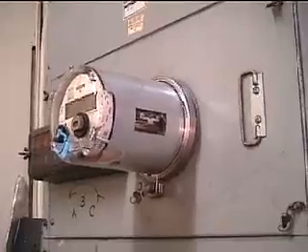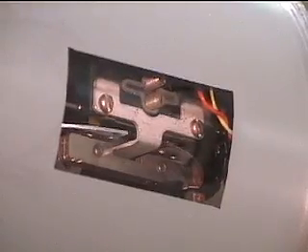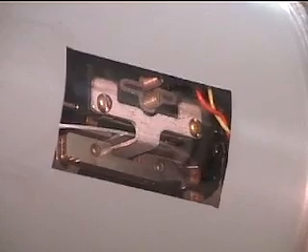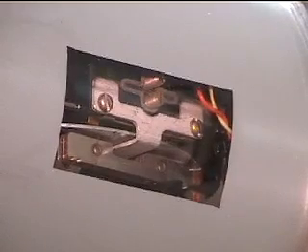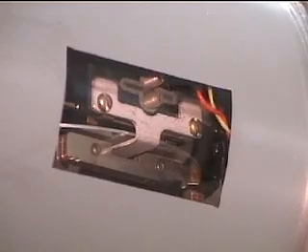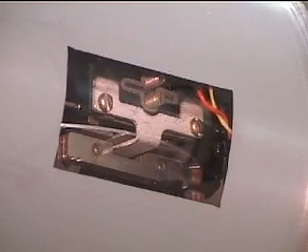This power meter illustrates how the vehicle's power flow affects the building's power consumption. Initially, the wheel spins with the normal building load. When the vehicle battery charger is turned on, the wheel spins faster. Now the charger is shut off, and the discharge function is enabled. The discharge power slightly exceeds the load in the building, so the meter spins backwards. Now the discharge is stopped.